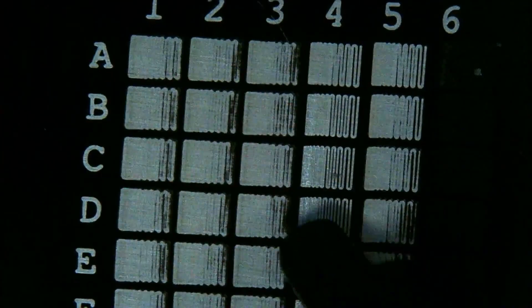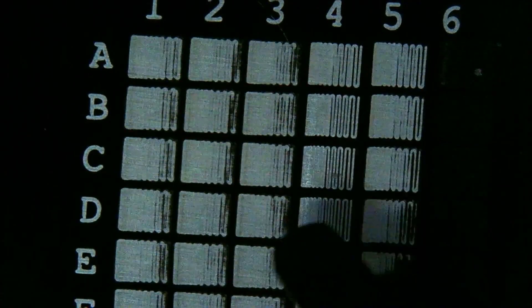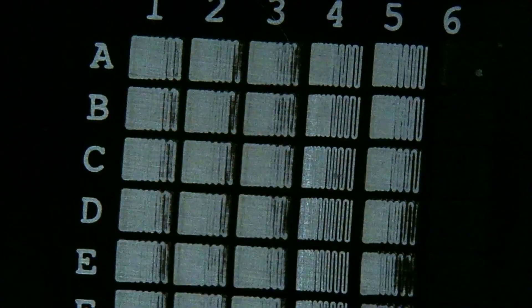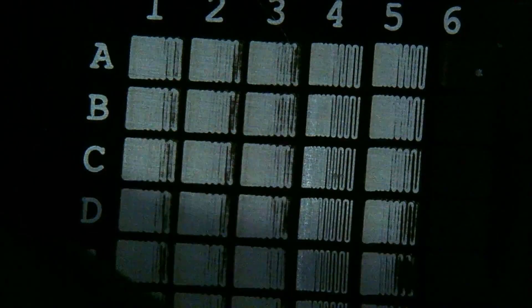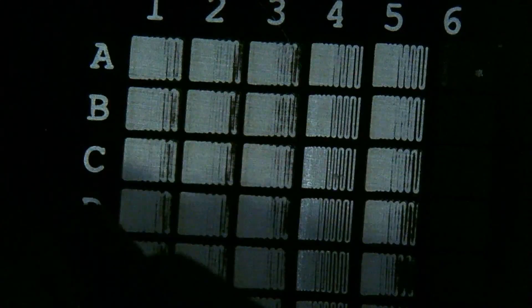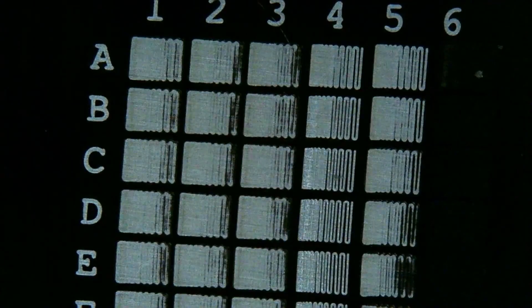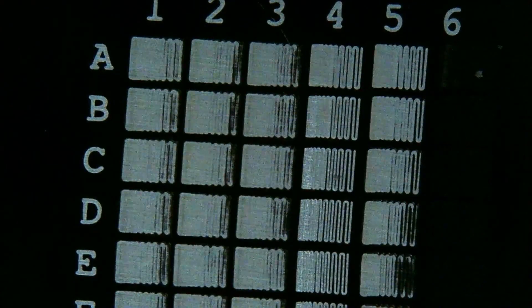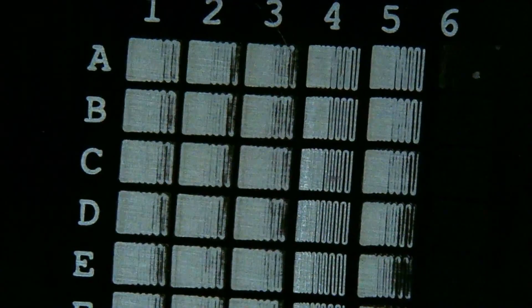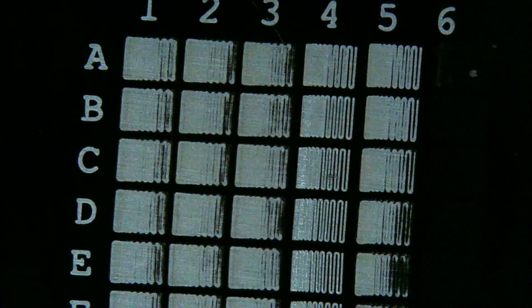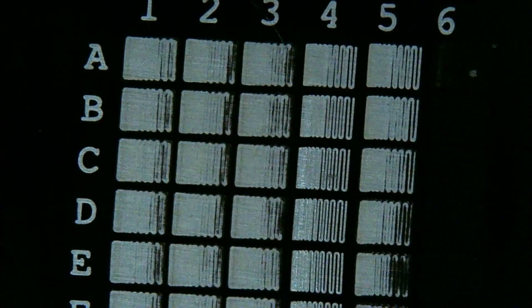We're looking for the clearest one. If you look towards the middle, you'll see the solid square starts to turn into a squiggly line. We're looking for the one with the most detail. It looks like D4 has the most detail as we can see more of the black between each squiggle. It's a subtle difference, but as long as we're close, we'll get a good result.